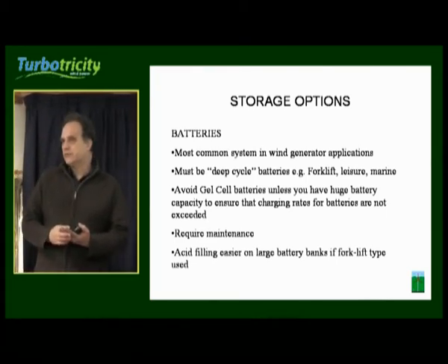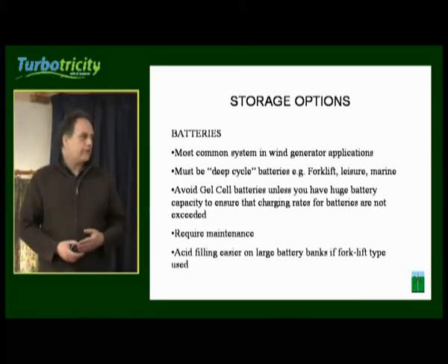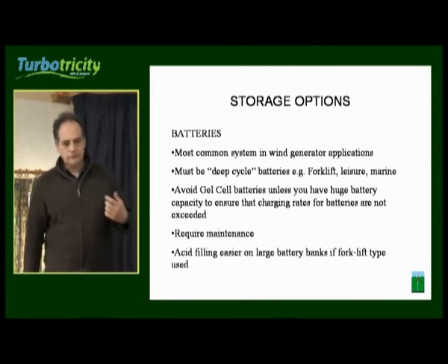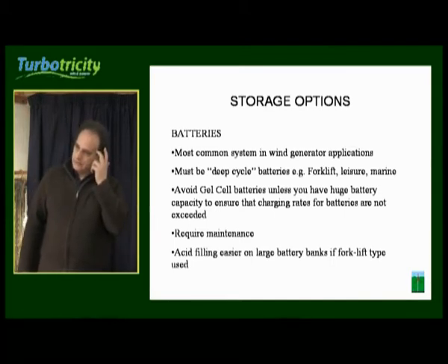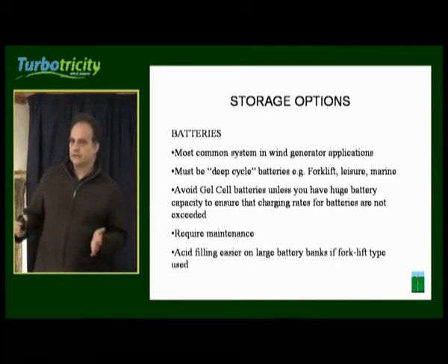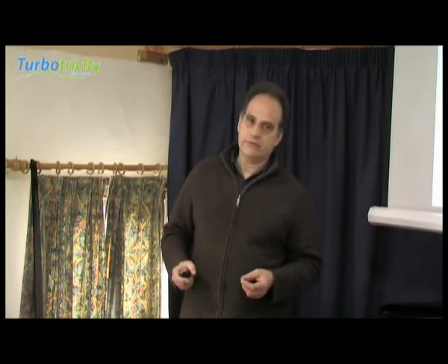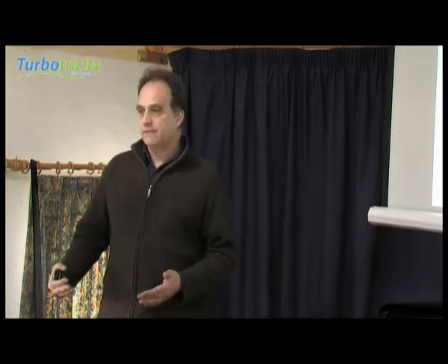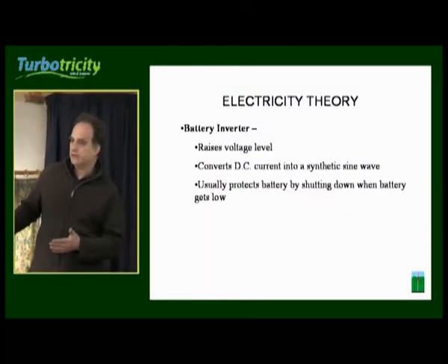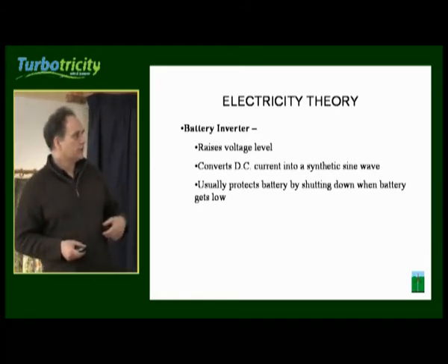Even so, most batteries like forklift batteries are not designed to sit on low charges for long periods of time. If you really want to look after batteries in a battery-based wind power system, you should ideally either seriously oversize your batteries so you're not deep cycling them too much, or have a standby generator to recharge them — if the weather forecast is looking bad, recharge your batteries. You would then have a battery inverter that converts the low voltage DC into high voltage AC, typically using a transformer to produce a synthetic sine wave.